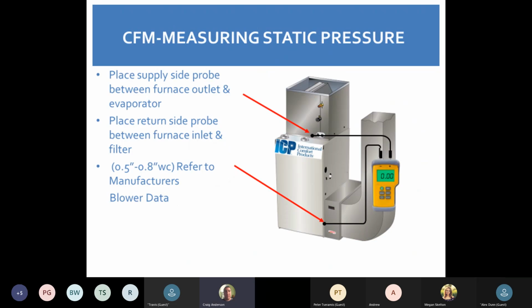Static pressure is another big thing. Our fan motors are looking for a static pressure. They're running to look for static. So we have to be mindful. Good static pressure is about 0.5 to 0.8. Anything out of that, if you're too low, then your motor starts hunting. It starts looking for static pressure.